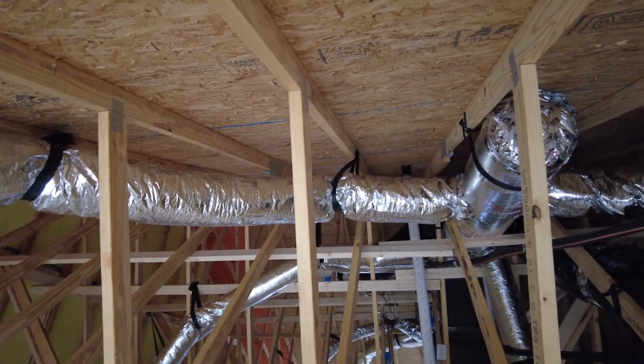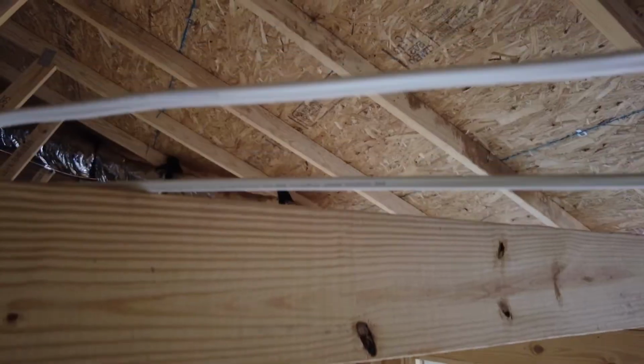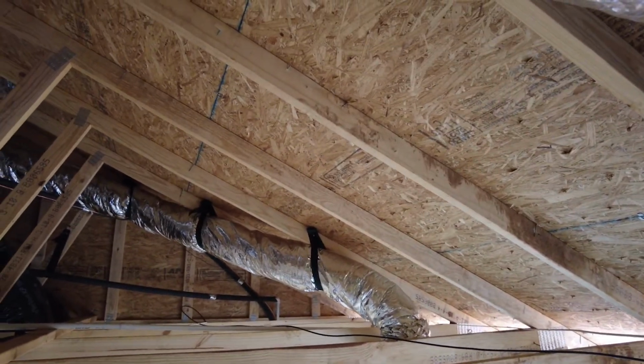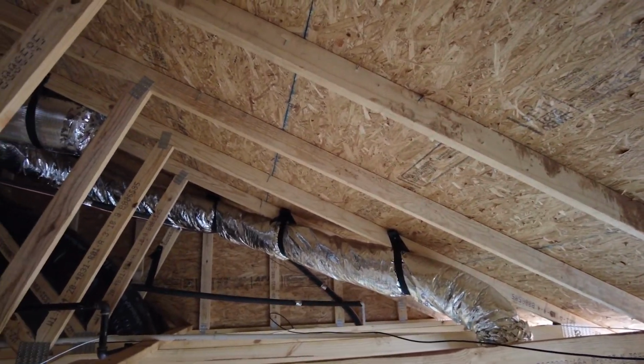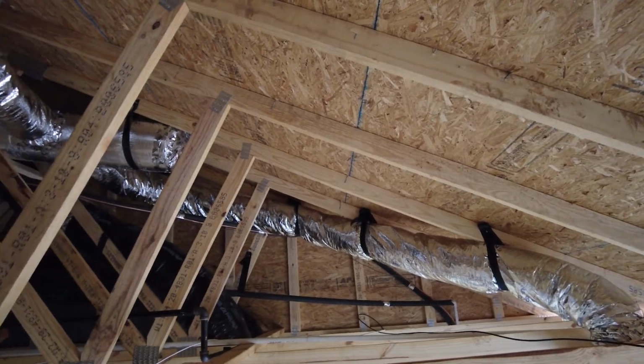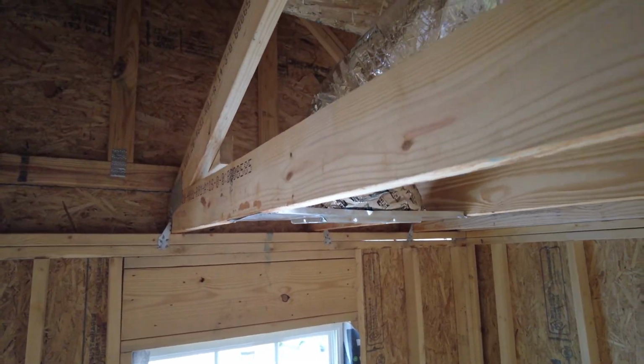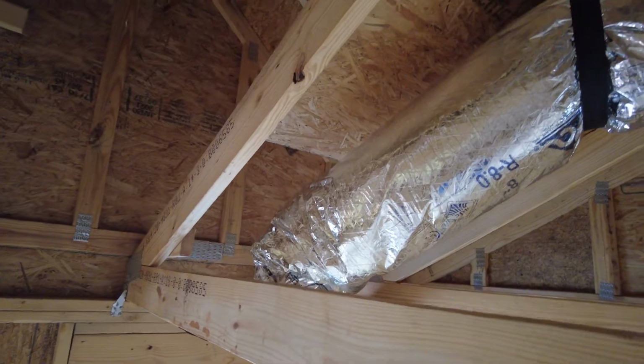One of the things I see so often is installers will actually strap the ductwork to the underside of the roof deck. It's bad enough that the ductwork is in an unconditioned attic, but it's even worse to strap the ducts to the hottest surface in that attic, the bottom of the roof deck. But it's common practice. I see this all the time.